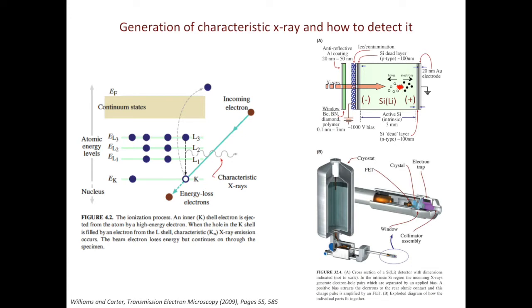There is an electrical bias applied across the detector, so electrons will be attracted in one direction and the holes in another direction. This will generate electrical pulses, and the detector knows there's X-ray hitting the detector. Higher X-ray energy will give rise to more electron hole pairs. This is how the detector measures the energy of X-ray.